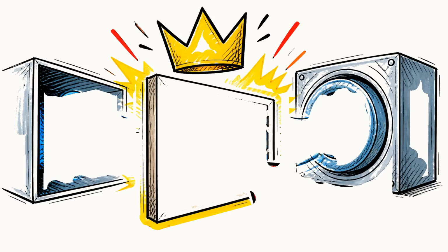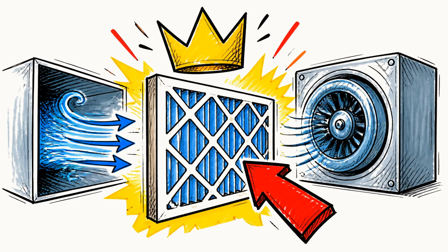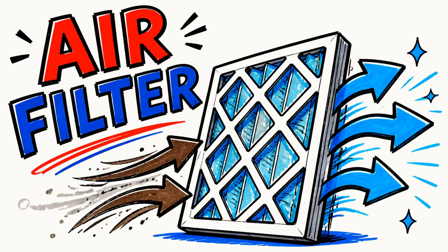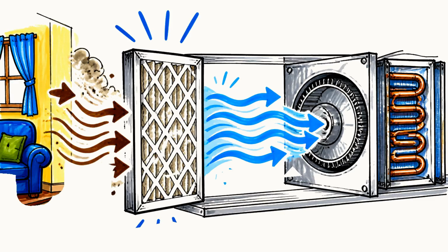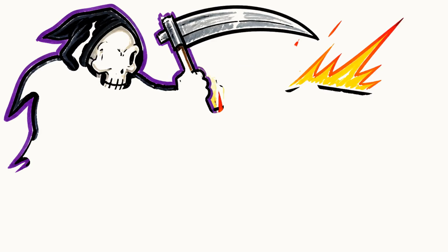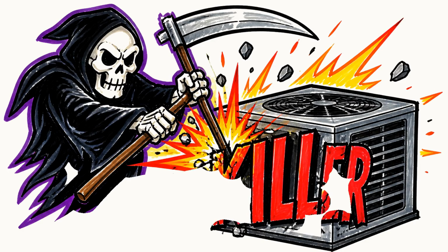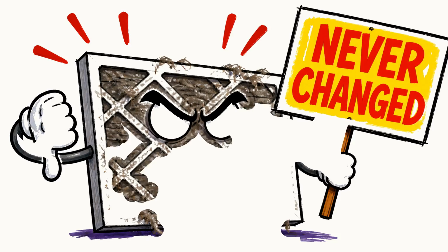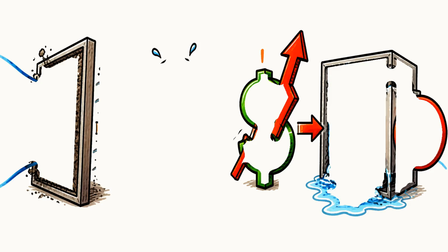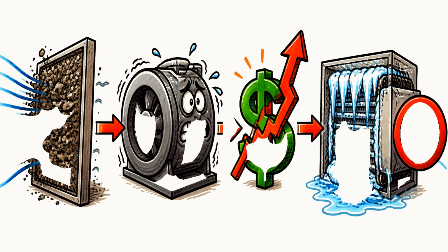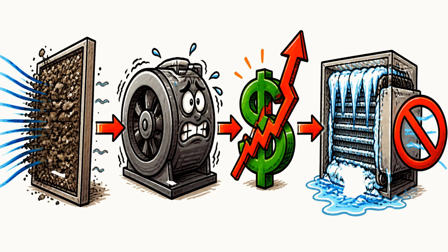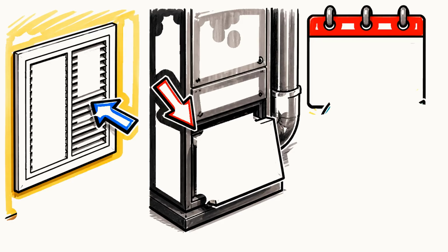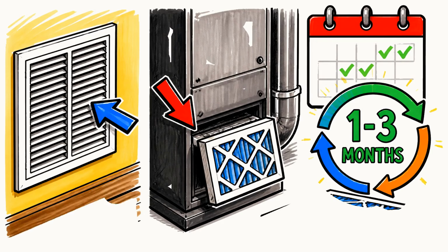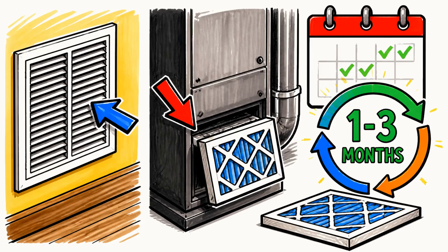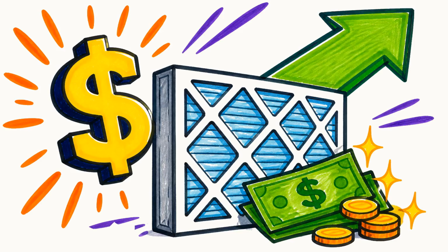Sitting right in that return path is the cheapest and most important part in the whole system, and it is the one nearly everyone forgets, the humble air filter. Every bit of air your house breathes gets pulled through it before it reaches the fan and the coils. If I had to name the single thing that kills more of these systems than any dramatic failure, it would not be some exotic part, it would be a filter nobody changed. A clogged filter chokes the airflow, makes the blower strain, drives your power bill up, and in summer it can freeze your cooling coil into a solid block of ice, so no cold air comes out at all. It lives at the return grill or in a slot near the bottom of the furnace, and a thin 1-inch filter wants changing every 1 to 3 months. That is the highest payoff few dollars you will ever spend on this thing.